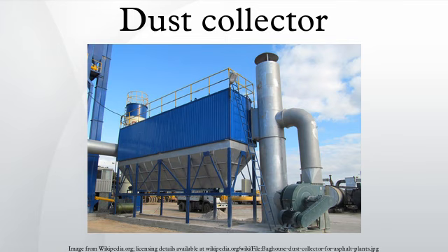Reverse airflow gives the bag structure. Dirty air flows through the bag from the inside, allowing dust to collect on the interior surface. During cleaning, gas flow is restricted from a specific compartment. Without the flowing air, the bags relax. The cylindrical bag contains rings that prevent it from completely collapsing under the pressure of the air. A fan blows clean air in the reverse direction. The relaxation and reverse airflow cause the dust cake to crumble and release into the hopper. Upon the completion of the cleaning process, dirty airflow continues and the bag regains its shape.